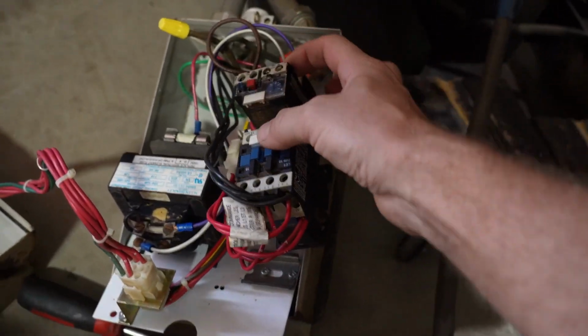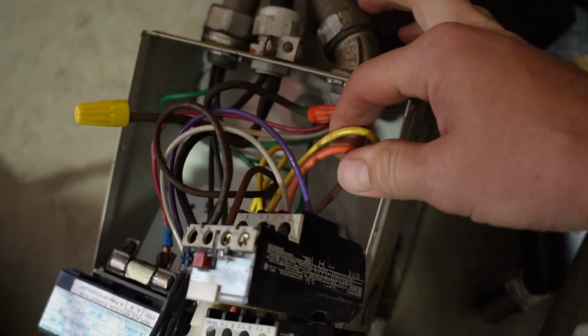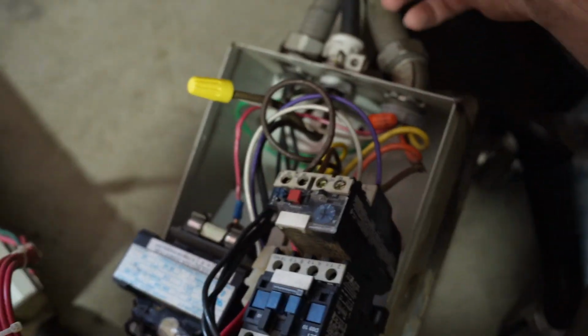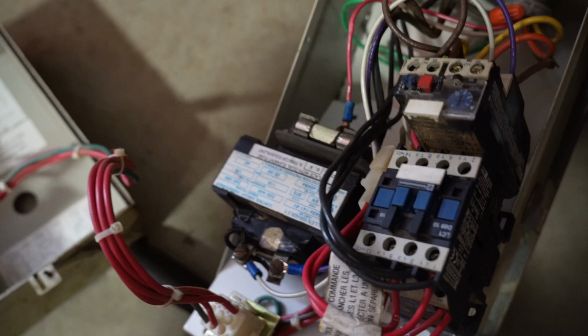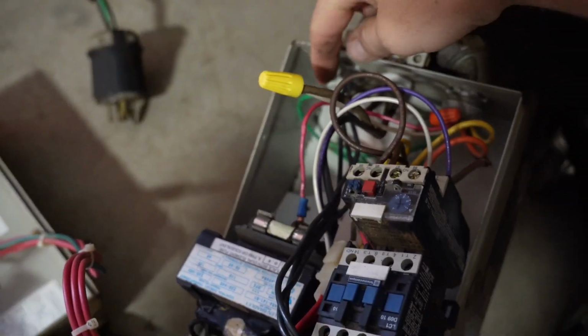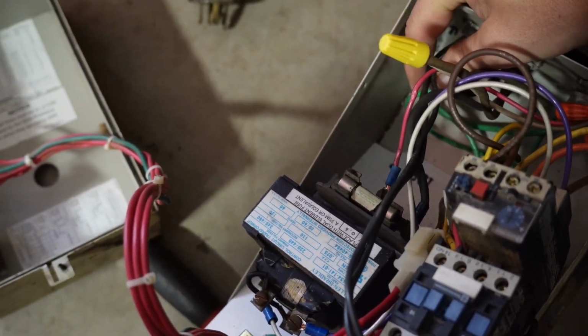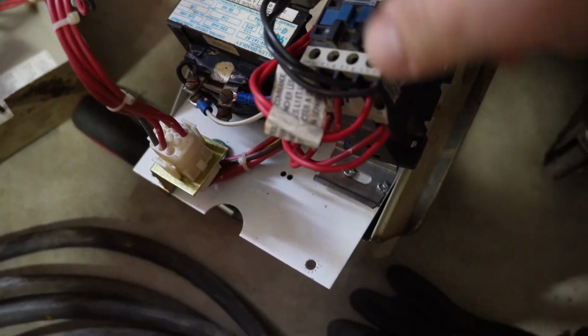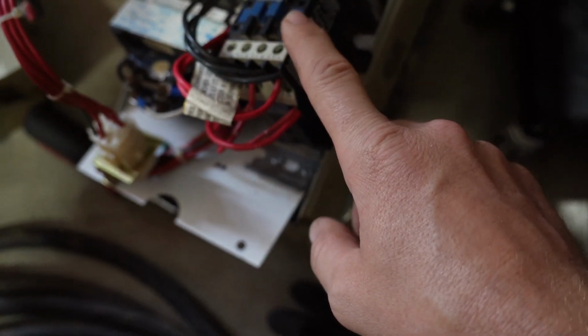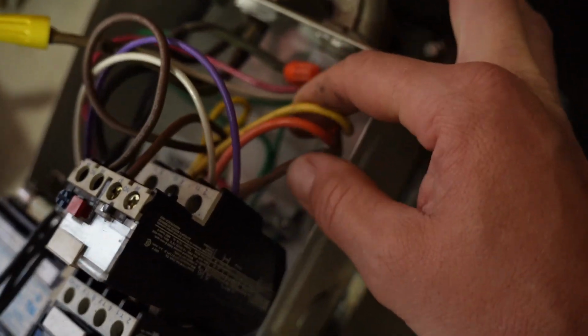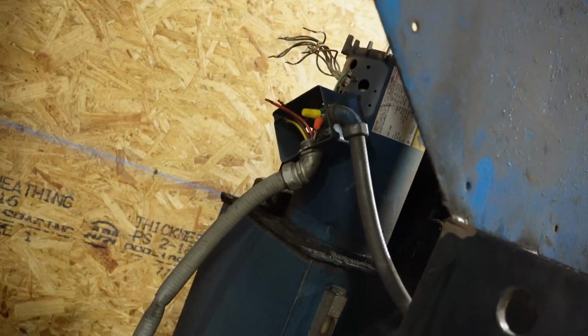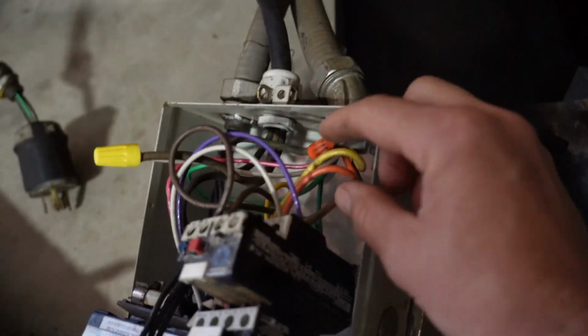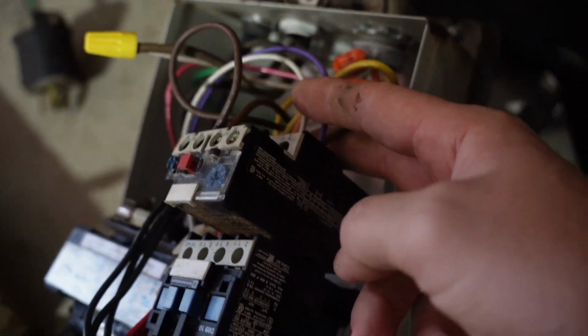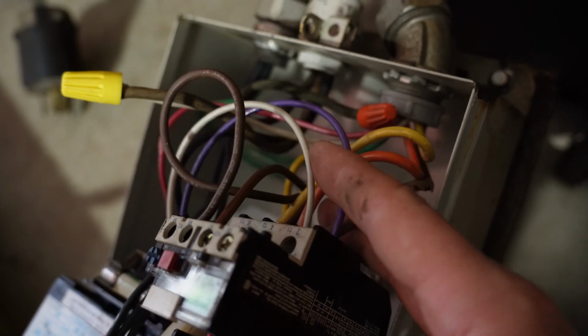All right, so here we've got, let's start here. We'll start with the power in from the wall. Right now, this is our power in from the wall. Comes in right here. We've got our 3 hots and our ground. Those 3 come up here. They go into the top of this Allen Bradley start-stop. Then they come back out down here, and that's what goes to the motor up there. Then they also have tapped right into 2 of the 3 lines going to the motor.